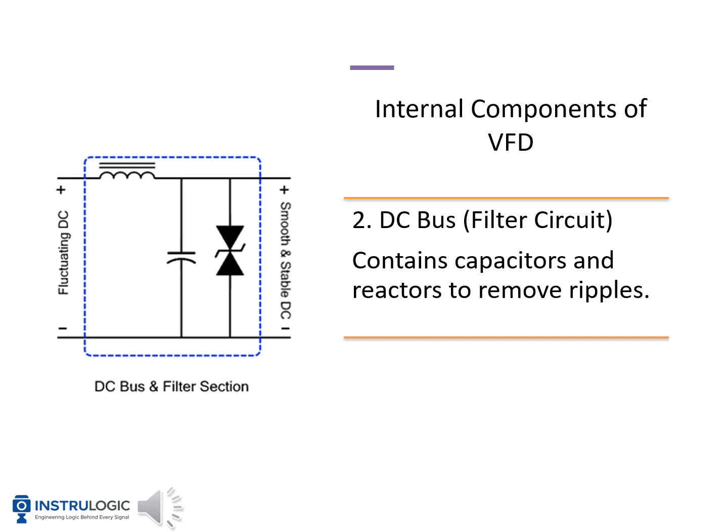Let's talk about the second internal component of a VFD, which is the DC bus, also called the filter circuit. After the rectifier converts AC to DC, the DC is not perfectly smooth — it has ripples. The DC bus section removes these ripples and makes the DC stable using capacitors and reactors (or inductors). Capacitors store and release energy to smooth out voltage fluctuations, while reactors help reduce current ripples and improve power quality. The fluctuating DC enters the filter, and the output is a smooth, stable DC ready for the inverter stage.